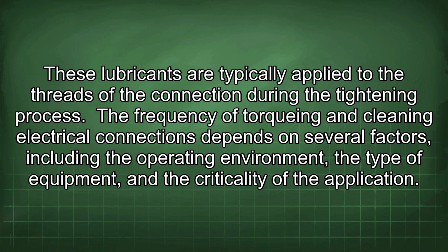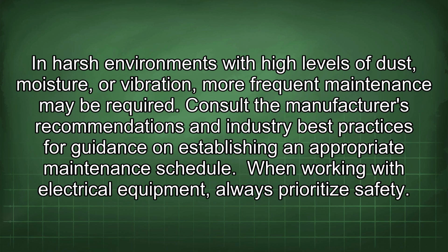The frequency of torquing and cleaning electrical connections depends on several factors, including the operating environment, the type of equipment, and the criticality of the application. In harsh environments with high levels of dust, moisture, or vibration, more frequent maintenance may be required. Consult the manufacturer's recommendations and industry best practices for guidance on establishing an appropriate maintenance schedule.